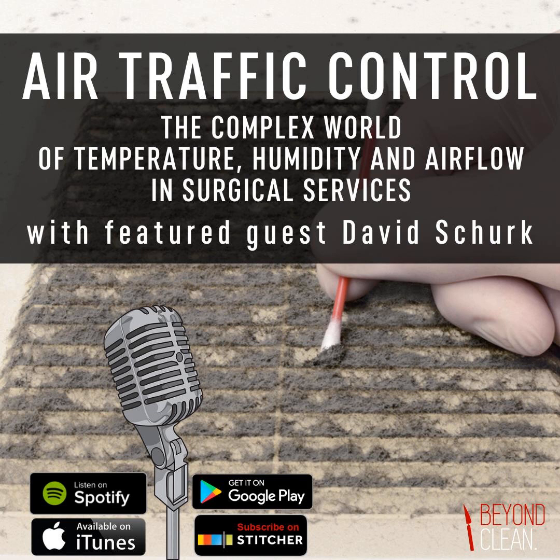the surface. So it'll condense on walls, on ceilings, on supply grills, on instruments, on scopes and lenses, everything. And all of a sudden, you've got an environment where moisture has condensed and begins to drip from surfaces. And obviously, at that point, the patients have been compromised. The docs are mad as hell. The potential for mold growth has now occurred in the space. So the space has to be reconditioned before it can be reused. So they have to shut the OR down and scrub it.